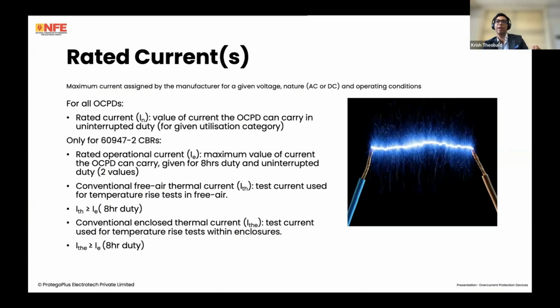Generally, these 60947-2 circuit breakers are meant for competent persons to operate. These are either rated to run throughout the day or to run under constant load for about 8 hours a day. So there are two rated current values that are given by the manufacturer. Then there is also the conventional free air current. So if the OCPD is installed in free air, there's a certain test current that is used to see how much the temperature rises inside the internal components.